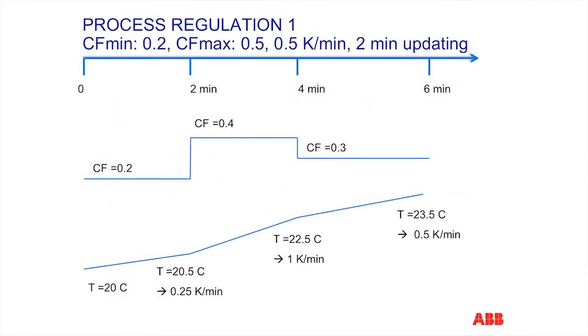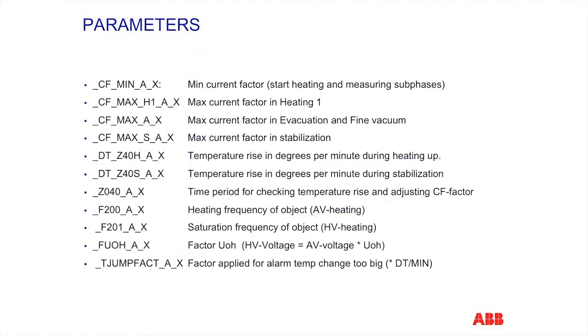You can see the temperature relationship for the process throughout the various steps. The temperature reaches a maximum value in each step as determined by the set points T1, T11, and T25. As you can see, these values are the average of the low and high voltage winding temperatures. The current factor is regulated on an updating schedule of 2-minute periods. The computer measures the rate of temperature rise and adjusts the CF to meet the set point requirements. As previously stated, the CF value cannot exceed the maximum set point value regardless of the needs of the heating algorithm. Shown here are some of the key parameters that control the heating cycles.